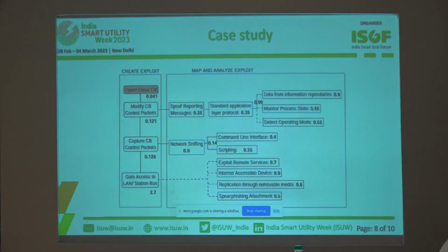So what we have done is, we are incubated at IISc Bangalore and we have a test bed there. Based on that, we have created exploits on the substation network, to first gain access to the LAN or station bus, capture the circuit breaker control packets, modify them, and accordingly open or close the circuit breaker.